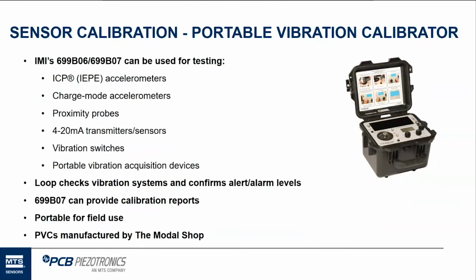A lot of people spend a lot of money every year sending away their portable vibration data collector to the OEM or the manufacturer to get it calibrated. I've heard that costing sometimes $5,000 per data collector. Well, you can do that with a portable vibration calibrator and get the same calibration done at a much lower cost if you own this. Again, as I said earlier, it's a low cost entry device, so it's not super expensive, budget friendly, so to speak.